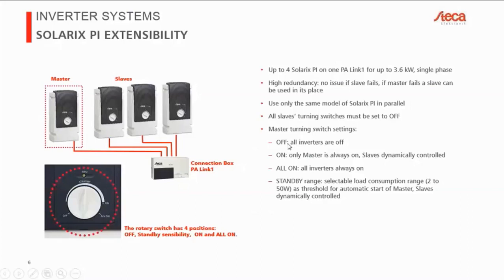Off means all of the inverters are off. So you have virtually no self-consumption. If you're using a weekend house, for example, the customer can simply turn the switch from the master to off and be sure that all of the inverters in parallel are all off.